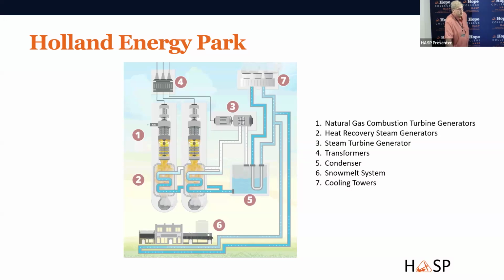And so one of the things that they learned was when they first started in the summertime, well, we don't need to run snowmelt. However, what happened was they had calcium buildup. So they realized they had to change the chemistry, and you ought to see the water purification in this facility so it doesn't affect the turbines and so forth, and the gas cleaning that has to go on to make sure there's no impurities in the system. It's amazing. Anyhow, so what they do now is during this time of year, the snowmelt is running at about 5 pounds per square inch, or 5 psi. In the wintertime, it's 35 psi. So they still circulate water, but just not at the same rate and under the same pressure.